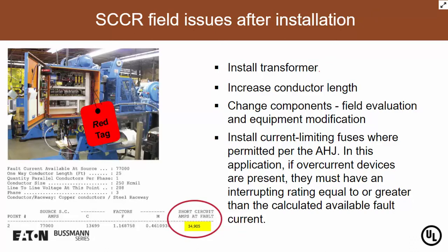And so there's 4 ways that I see that we can change this machine that's possibly already installed or being installed, where they didn't realize that the available fault current was higher than the SCCR. So you can add a transformer, a high impedance transformer, to reduce the fault current. You can run longer lengths of conductors to reduce the fault current. So the first 2 options are reducing the fault current. And then the next 2 options are increasing the SCCR of the machine and of the industrial control panel itself.